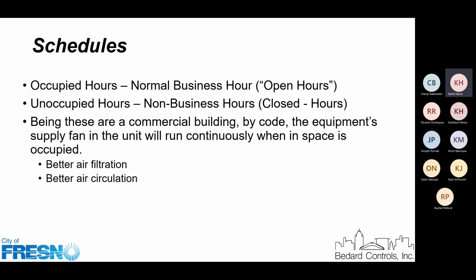So a lot of times, because it's not hot air, it's not cold air, you may think the equipment's not running. The equipment will turn on the heating or cooling as required to maintain the set point in the space, but the fan will continue to run continuously during occupied hours.